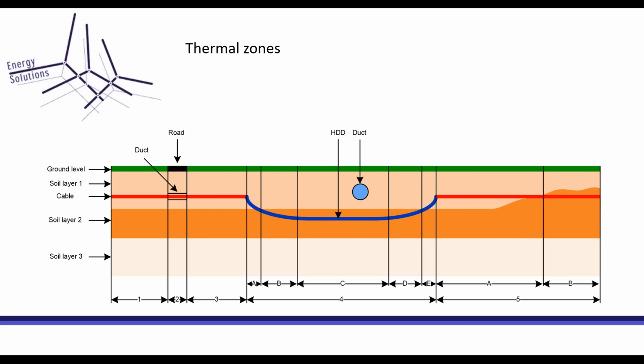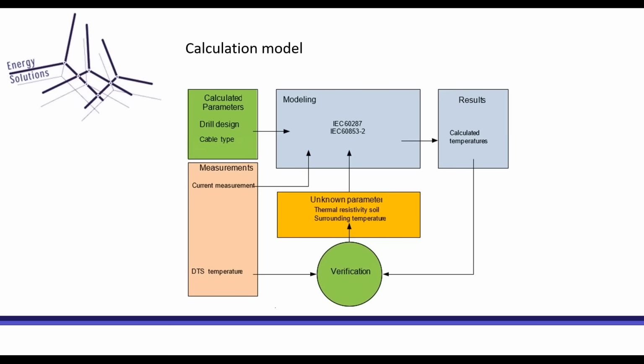Still, one of the quite unknown parameters is the thermal resistivity of the soil, which can change during the season. In contrast with overhead lines, underground cables are not really directly influenced by the weather, but indirectly they are, due to the surrounding temperature that will vary during the season. So to verify if this is working, if you calculate the right values, you use a model from the IEC, but also a verification loop to calculate the temperature response. The calculated temperature response is verified with a temperature that is measured on the cable. And if there's any difference between the measured and the calculated temperatures, then you need to adjust the thermal resistivity in the model or the surrounding temperature. Or there could be something else happening that needs to be investigated.